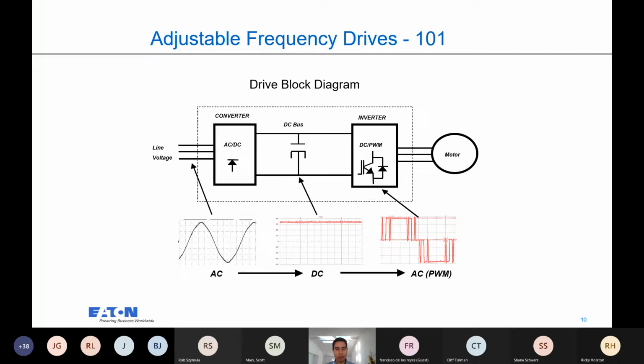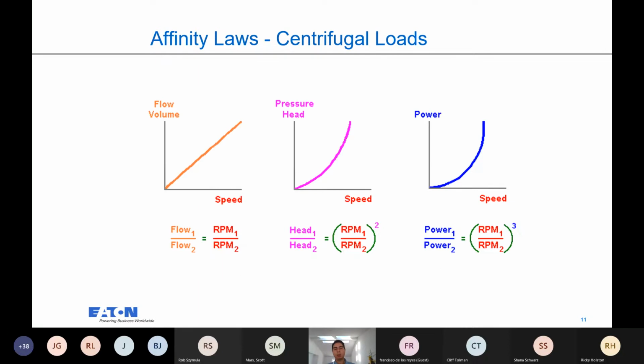let's go through a few things here. How to achieve energy savings with a pulse width modulated wave. With the pulse width modulated wave, the flow and the hertz, GPM, RPM are proportional. Your head is a square and your power is a cube. These are the affinity laws. This is most common in variable torque loads. We will discuss variable torque versus constant torque in a few.